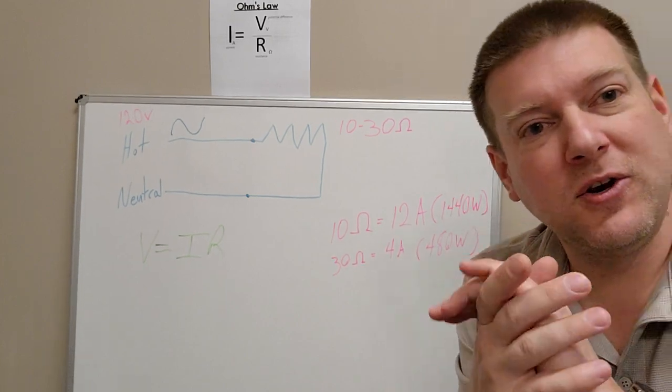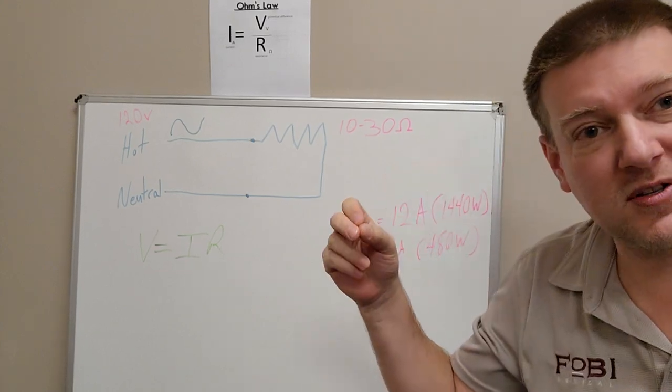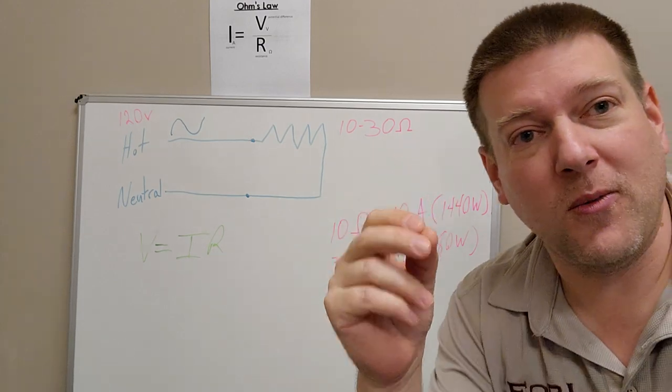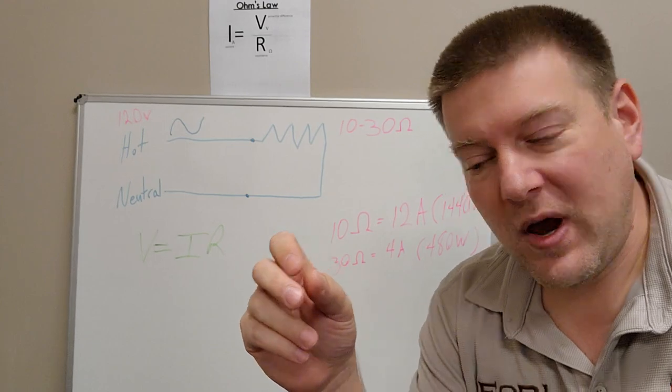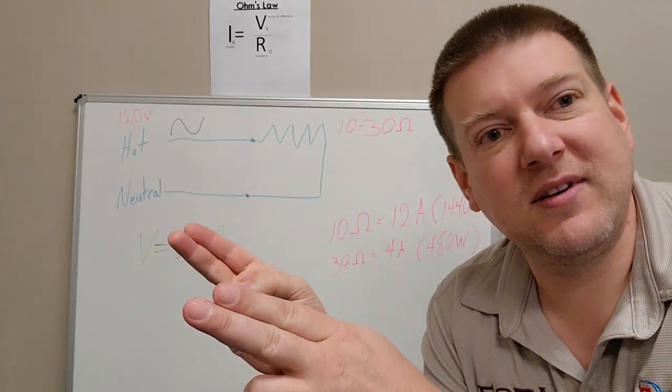Your heating element is basically a giant resistor with values between usually 10 and 30 ohms. When you're testing a resistor, you have to disconnect one leg from the circuit and now you can test it.